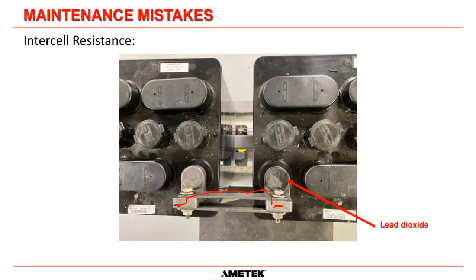As you can imagine, if somebody hadn't tightened down these bolts here and these were loose, you would have a loose or high resistance connection between this point here and this point here, and we need to be able to find that when we're doing our maintenance.